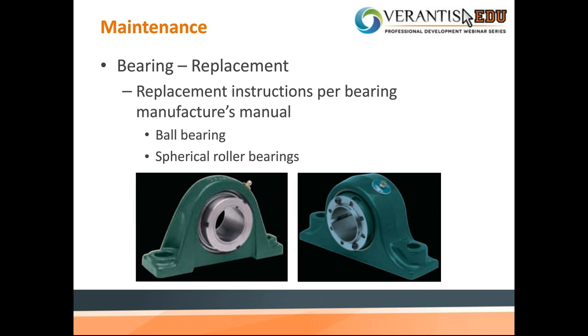Junior, any other types of bearing failure type issues that come up? I mean, we've talked about not using the proper grease. Well, proper lubrication. Make sure it's whether it's the NLGI 2 lithium based, or if it would be a polyurea or clay, whatever your base is. Be sure to use the proper lube. Too much lubrication can cause overheating of the bearings, which in turn, if it's an excessive temperature, could cause the seals to be compromised and could let dirt and stuff into the bearing, which again would affect the bearing.